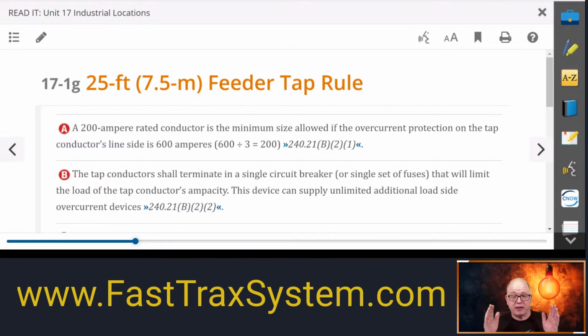That was the 25-foot feeder rule, where we're tapping a feeder and we have an overall length of 25 feet. So whether the secondary conductors were 25 feet and the primary was the same size as the feeder, which is not considered a tap at that point, or we're tapping and we have a maximum of 25 feet to supply a transformer. That was a previous episode. Check those out. All right, so 25 foot, we're all for transformers. Now we're talking feeders, just a normal everyday feeder.